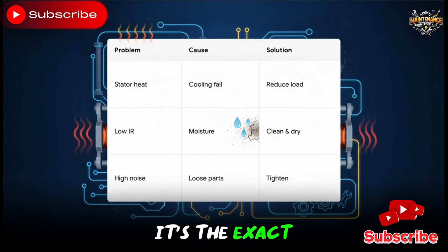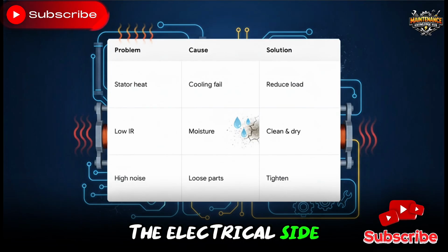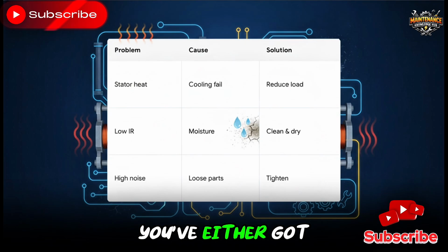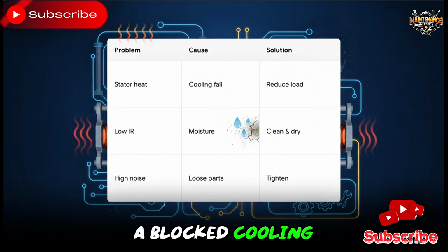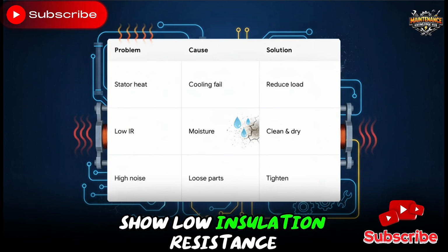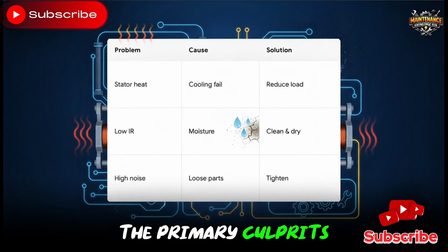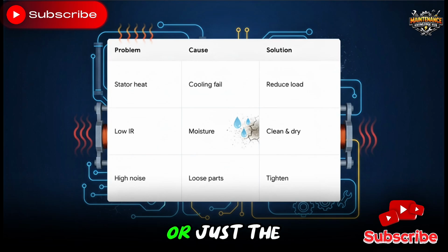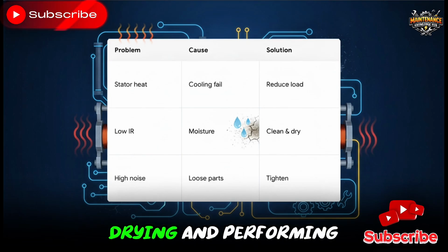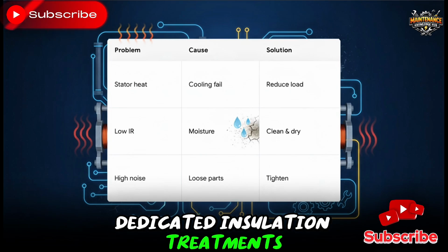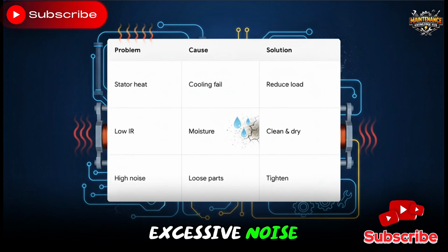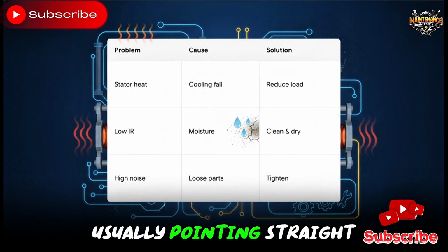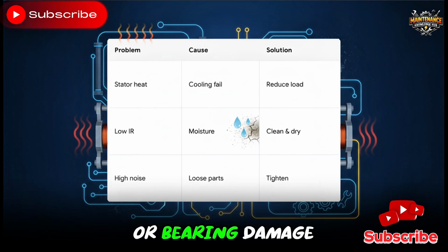And honestly, it's the exact same logic on the electrical side. If the stator is overheating, you've either got a cooling system failure, a blocked cooling passage, or you're just overloading it. If your electrical tests show low insulation resistance, the primary culprits are usually moisture, contamination, or just the natural aging of the materials. The fix there requires deep cleaning, drying, and performing dedicated insulation treatments. Even something like excessive noise has a direct mechanical cause, usually pointing straight to loose components or bearing damage that requires immediate tightening or replacement.